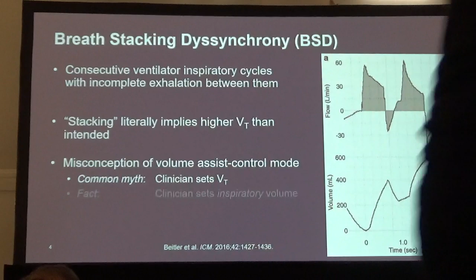And so what that means is that in a assist control mode, for instance, the patient triggers the ventilator or the time triggers the ventilator. The patient gets an inspiratory cycle, but the ventilator does not then turn into a vacuum and suck back out that air. It's only pushing the air in, and it relies on either passive chest and lung wall recoil or active patient effort for that air to come back out.